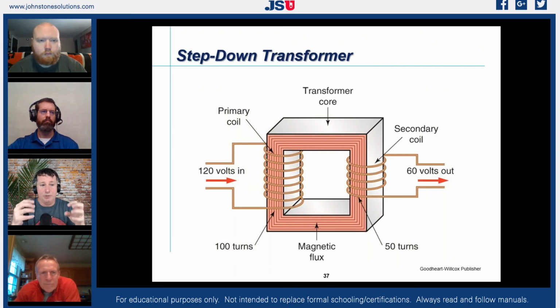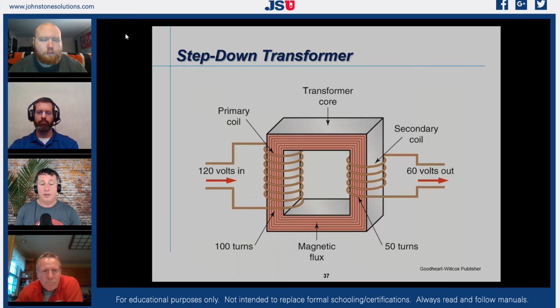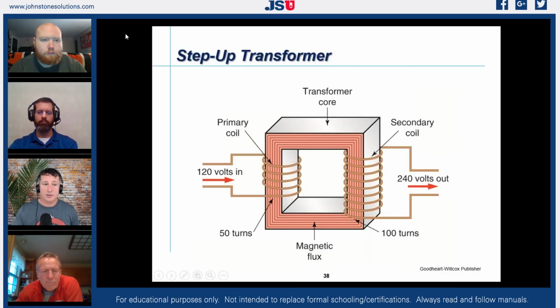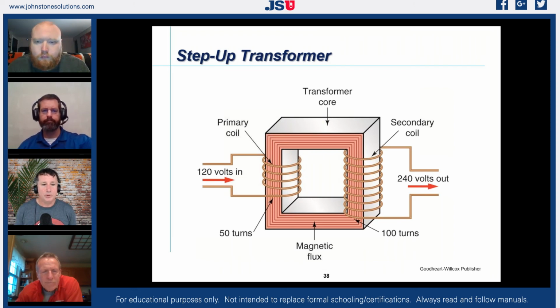We're going to have some vibration, some frequencies moving through those plates. If those plates are not tightly compacted and not made of consistent material, we can have vibrations within them, and we're going to generate frequencies. It very much comes down to construction and the amount of load, because if we're trying to pull more electrons off that transformer than it's capable of, we're also going to start generating heat and additional noise. So it's very much in the construction.